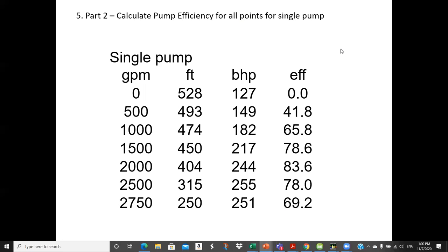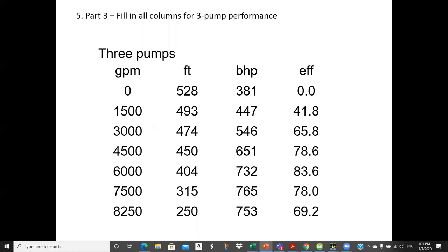Okay, I may have misspoken a second ago, so let me go through that again. Let's calculate this 41.8% efficiency. So 500 times 493 divided by 3960, and then divide that by 149, because that previous calculation is the water horsepower. This is the brake horsepower, and that ratio is the pump efficiency. When I punched it a second ago, I punched the 127, and it didn't come out, and I about had a heart attack. Anyway, they're correct. And then you do the same thing for the efficiency for the 3 pumps.